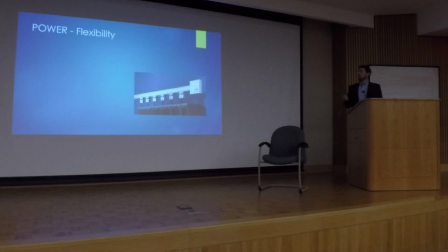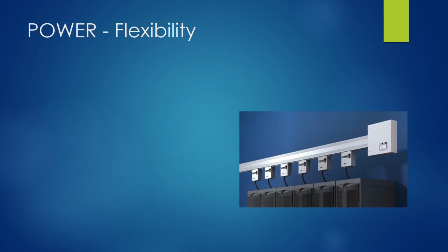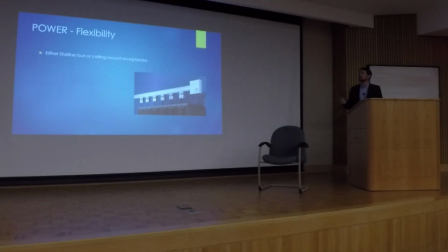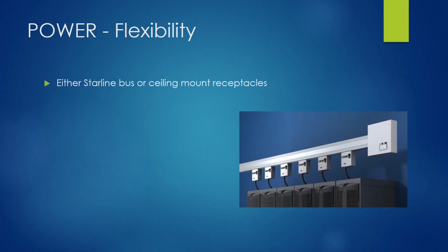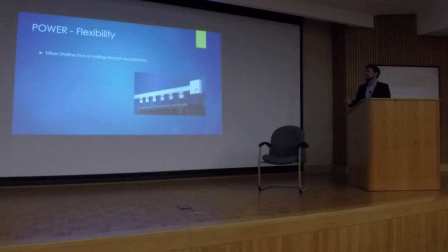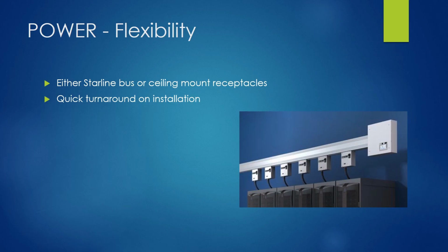Going on from space, power. First, we need very flexible power, because every HPC installation is unique. One way we do that is using the Starline bus, an overhead busway — though it could be any kind of busway — so you can take any type of receptacle, plug it into the bus, and suddenly have the exact right power configuration you need. It gives very quick turnaround, with any plug configuration or breaker size.